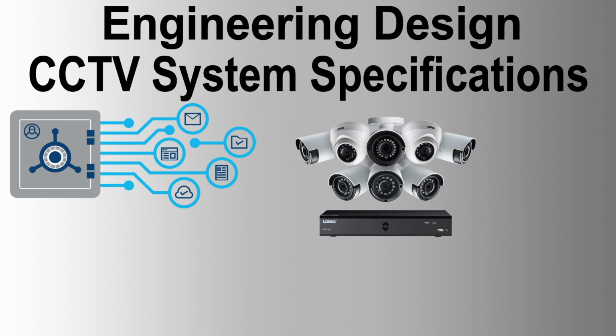CCTV communication network. CCTV system cabinets, control rooms at MPS, IPS, and MOT. The fiber optic cables from each camera in the pumping stations shall be terminated at patch panels located in respective control rooms. The patch panels may be wall-mounted units, or part of CCTV system cabinets. Station control rooms at each block valve station, tie-in station, and SPM stations. The coaxial cables from each camera shall be connected to CCTV cabinets located in station control rooms. The distance between the camera and the station control room is a maximum of 20 to 30 meters.